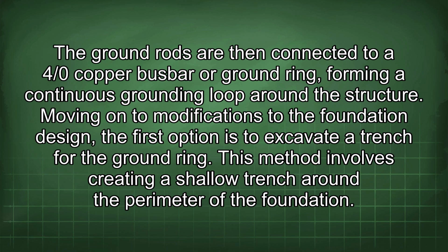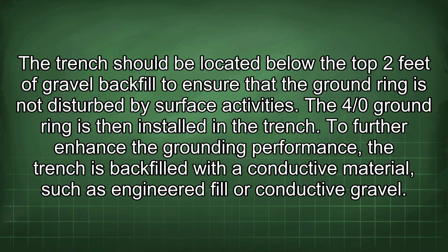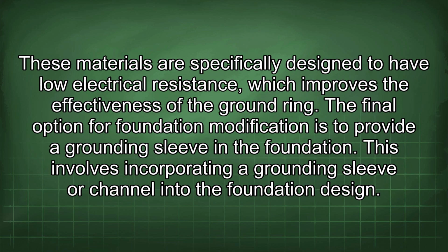Moving on to modifications to the foundation design, the first option is to excavate a trench for the ground ring. This method involves creating a shallow trench around the perimeter of the foundation. The trench should be located below the top 2 feet of gravel backfill to ensure that the ground ring is not disturbed by surface activities. The 4/0 ground ring is then installed in the trench. To further enhance the grounding performance, the trench is backfilled with a conductive material such as engineered fill or conductive gravel. These materials are specifically designed to have low electrical resistance, which improves the effectiveness of the ground ring.